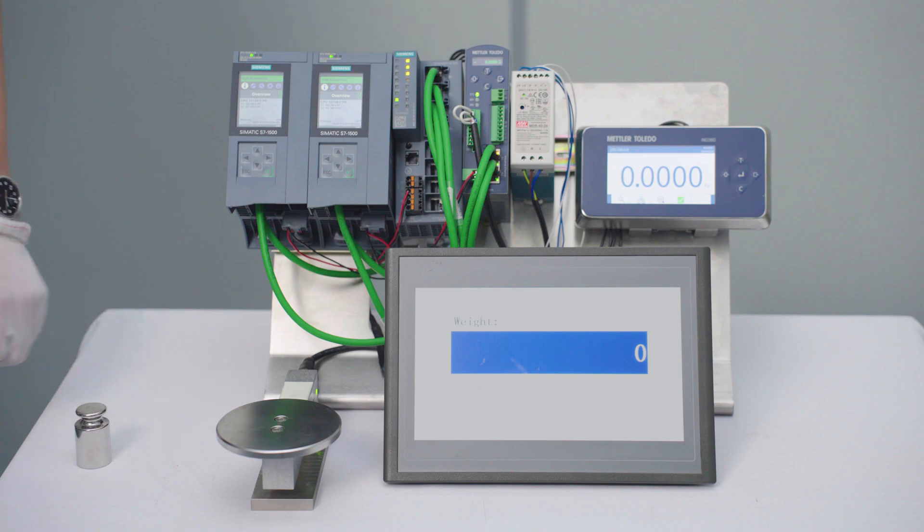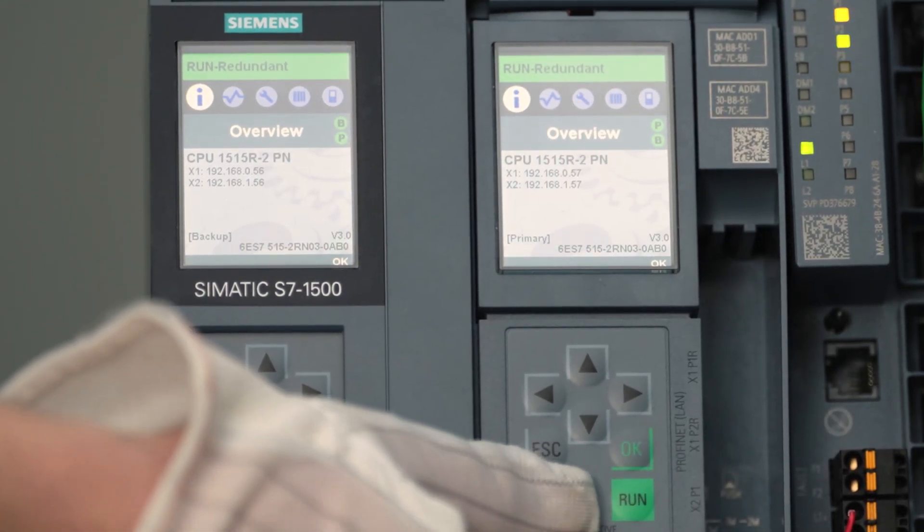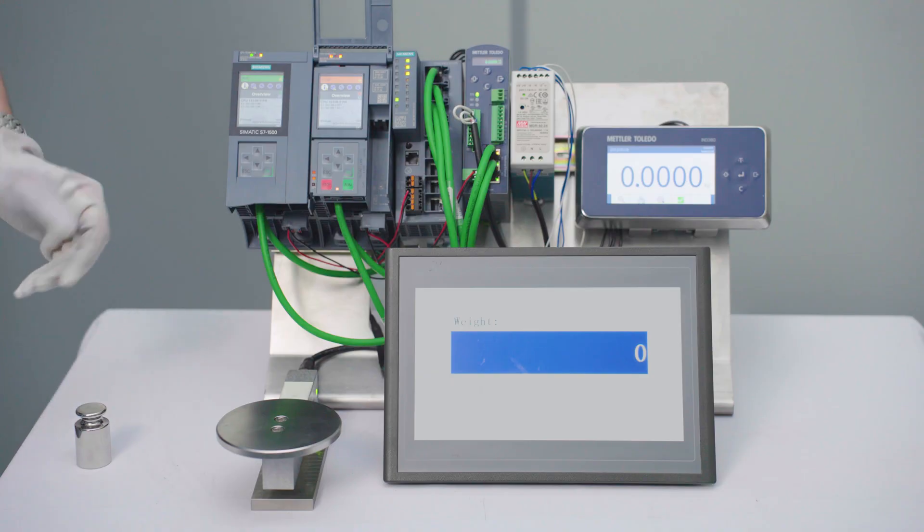Now let's simulate the failure of the backup PLC by putting this one to stop. So now the primary PLC is the only PLC executing.